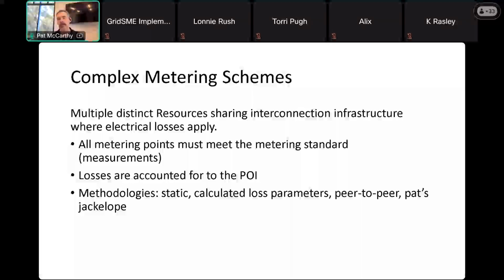So you could have a low side bus with 5 feeders. I guess with new NERC rules, you would still do that 100 megawatts a piece. So you're going to have 5 meters, one representing each resource at the 35 kV position, probably on a feeder breaker. And then you're going to have a big old transformer and a transmission line and some station service load between those meters and your point of sale, point of delivery, point of interconnection, point of common coupling. All of these things are often analogous, but not always. But the point of delivery, point of sale, essentially, is where all of the data at 35 kV needs to reconcile to. So often up at like 230 kV or something like that.